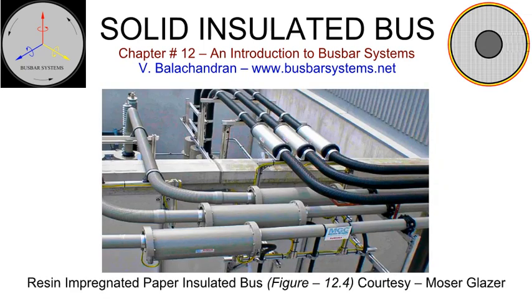Resin-impregnated paper insulated bus. Oil-impregnated paper wound conductors have found application in high-voltage cables, instrument transformers, and bushings since the end of the 19th century. Over the years, with the increase in the transmission voltage and the development of appropriately rated cables and condenser bushings for the transformers, their thermal and dielectric properties have been well researched, recorded, and documented. Impregnation of paper with oil is a comparatively risk-free process. Oil does not undergo a chemical transformation. If there be a minor deficiency in the dielectric properties of the finished product, it can be made good by reprocessing.